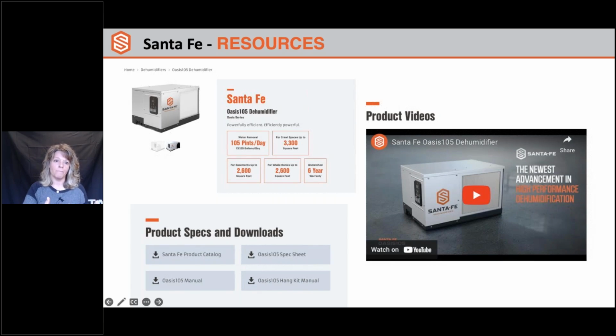Dehumidifiers, where we've seen in the past, maybe have been pigeonholed into crawl space and basements, and occasionally being added to HVAC. The reality is the more energy efficient our homes get, which means less run time on air conditioning, the more need we're seeing for dedicated dehumidification. And typically, the more energy efficient an air conditioner is, the less water it removes. So I would say in the last 5 to 10 years, the increase in commercial grade dehumidifiers being applied to homes has increased drastically.